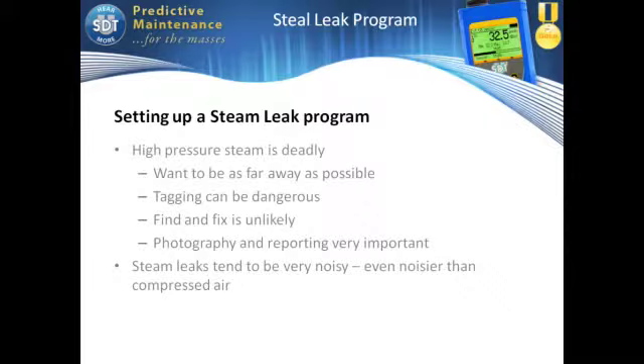Finding and fixing leaks is also unlikely. So photography is probably your best way of dealing with that. And steam is very, very noisy. So steam leaks are very easy to detect. Very easy to detect. Once you're on the steam side, the next thing we go into is steam traps. Again, a very simple test with ultrasound. Normally, the best combination is ultrasound and temperature. And if you have the ability to do both at the same time, then that is an added advantage.